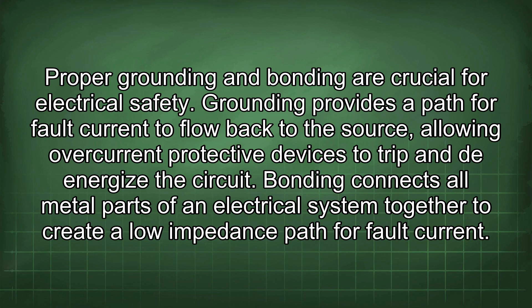Proper grounding and bonding are crucial for electrical safety. Grounding provides a path for fault current to flow back to the source, allowing overcurrent protective devices to trip and de-energize the circuit. Bonding connects all metal parts of an electrical system together to create a low-impedance path for fault current. The NEC requires that all electrical systems be properly grounded and bonded to minimize the risk of electric shock and fire.